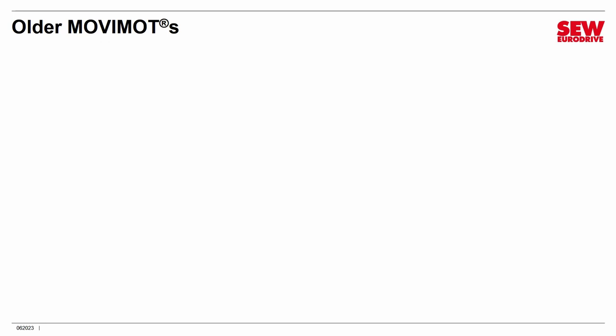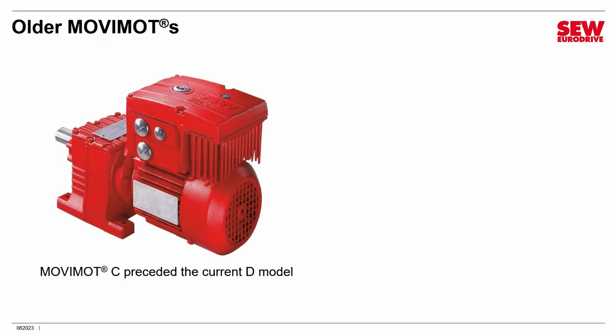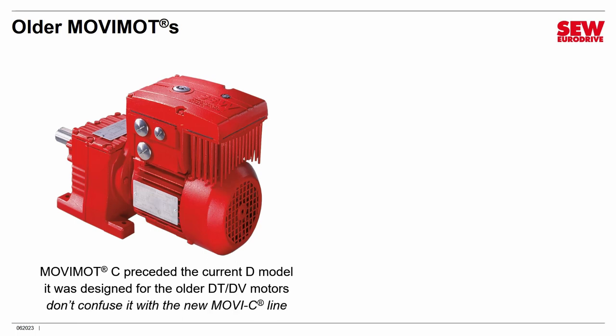Before we wrap up, let's briefly talk about the older discontinued MOVIMOTs. We are now in the fourth generation — there was an A, B, and C version. I want to talk about the C version since some are still in service. They look almost identical to the D version, but they worked with the older DT and DV motor line, which has been discontinued. They can't properly control newer SEW motors, so don't try. I also want to emphasize they have nothing to do with the new MOVI-C product line — that's an unfortunate naming overlap that causes confusion. The old C Movimots are legacy units, whereas MOVI-C is a brand new product line.